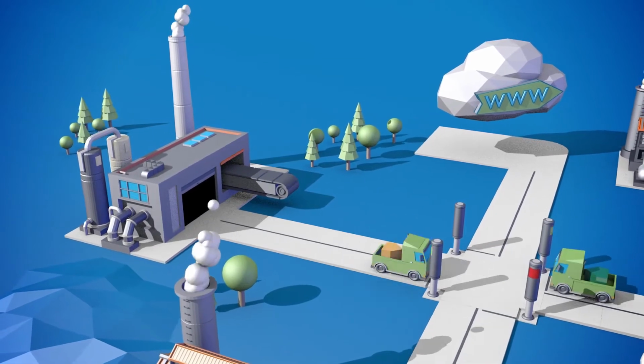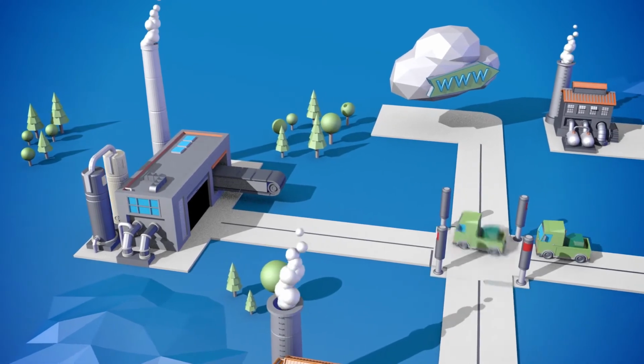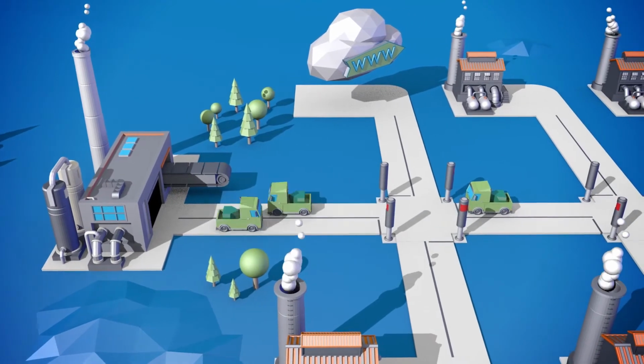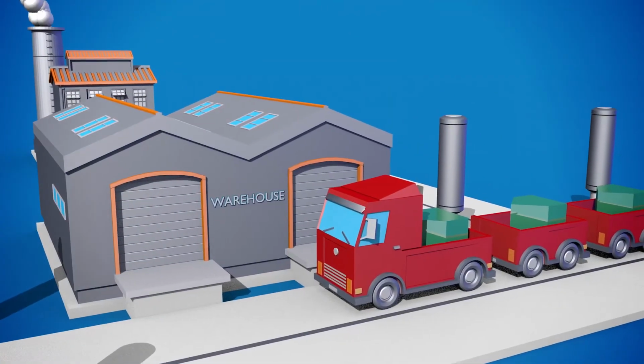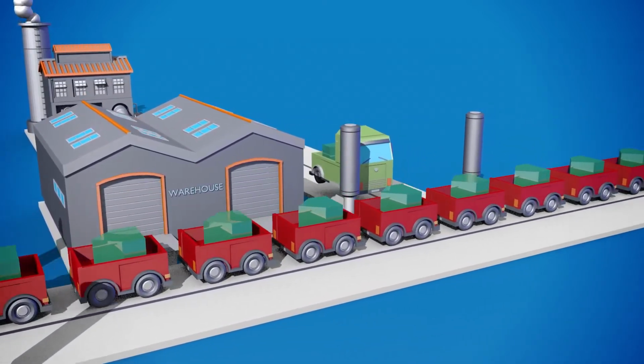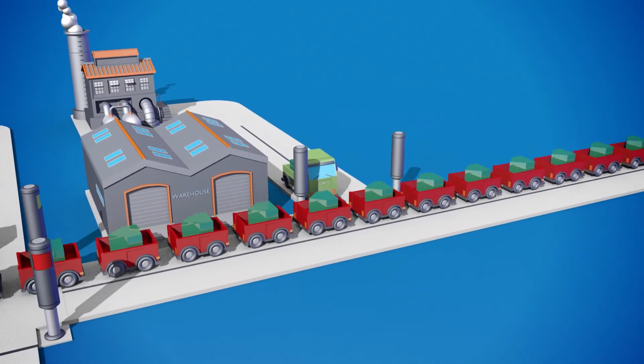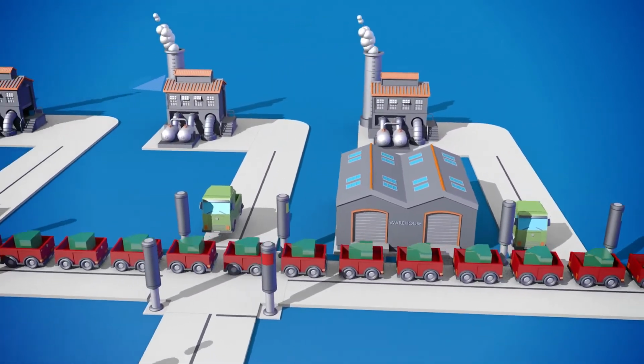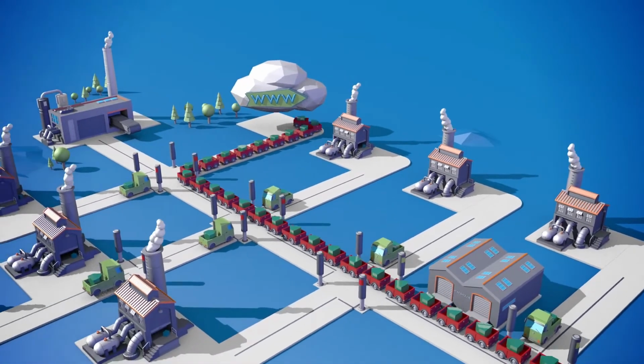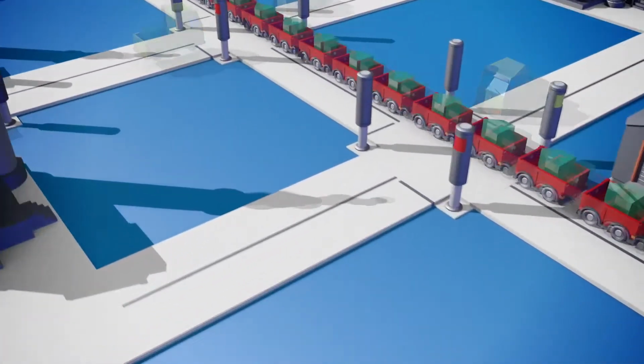However, acyclic data traffic also creates a load on the network. This includes data packages from TCP/IP traffic caused by a touch panel, data from production data acquisition, or even SNMP requests. TCP/IP packages are as fast as PROFINET telegrams, but larger, like a 40-ton lorry. Therefore, it puts a strain on the transmission routes for a longer time. Although, in principle, the PROFINET communication has right-of-way at network nodes, it may be slowed down by the TCP/IP communication. The load ratio between PROFINET and the TCP/IP communication should therefore be specifically adapted.